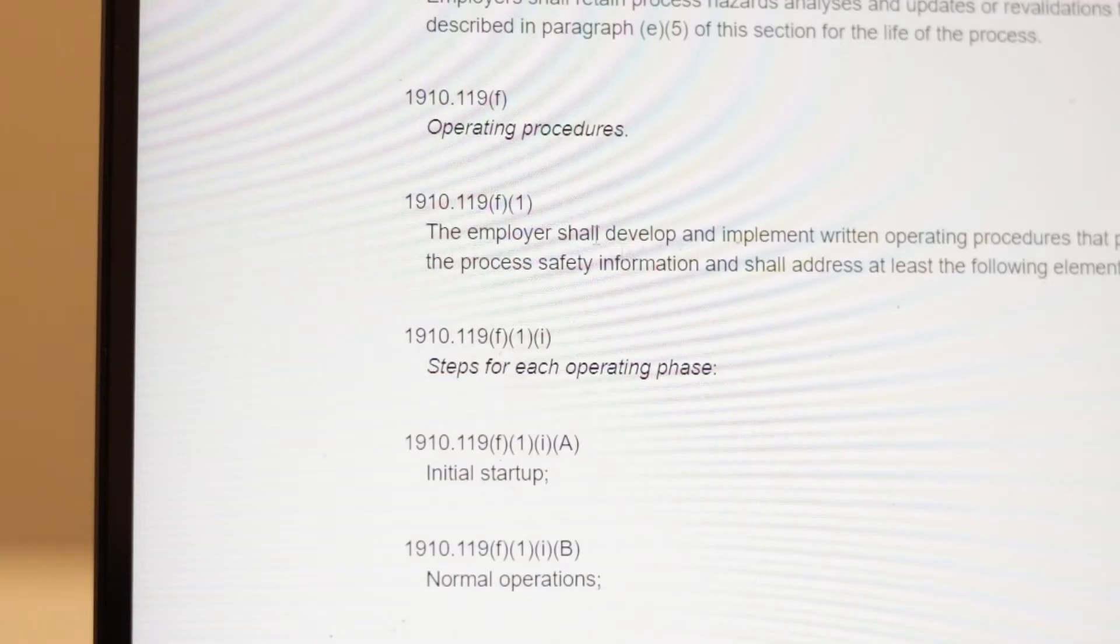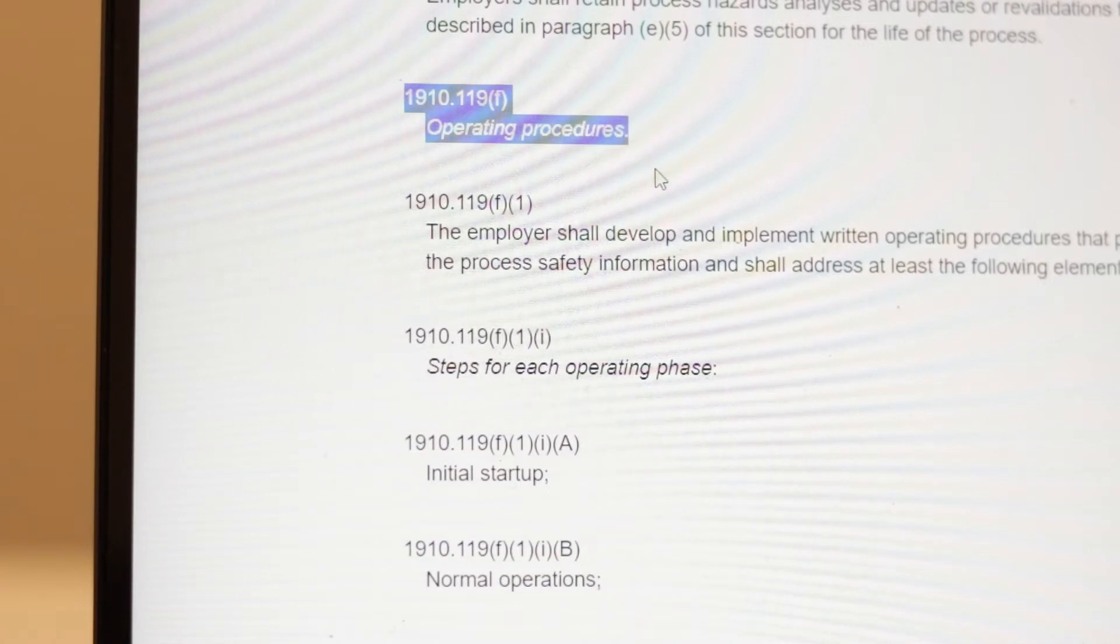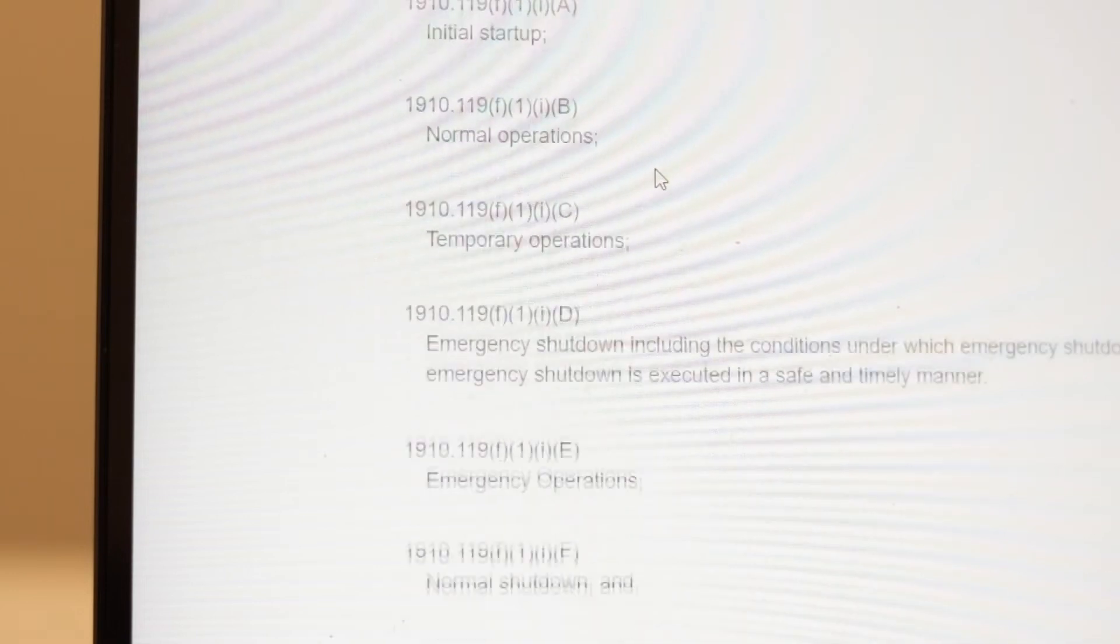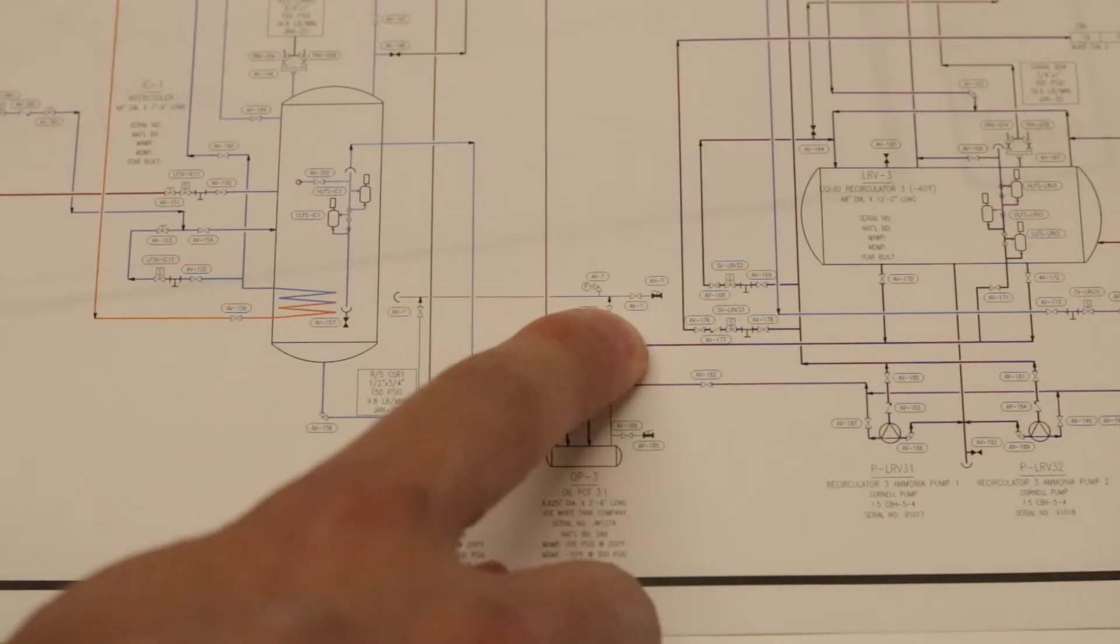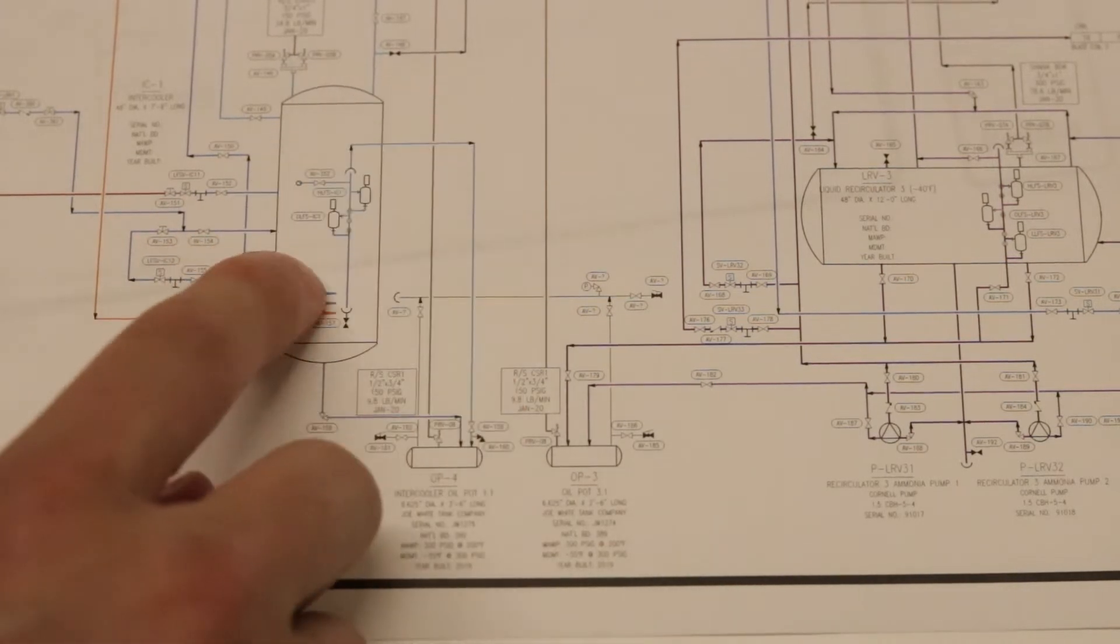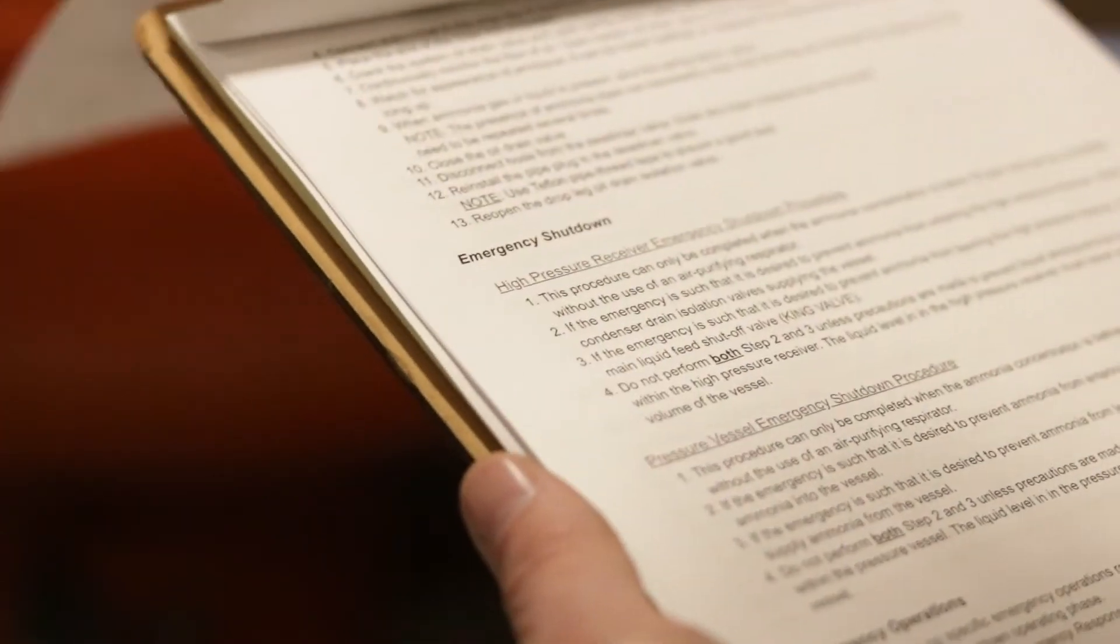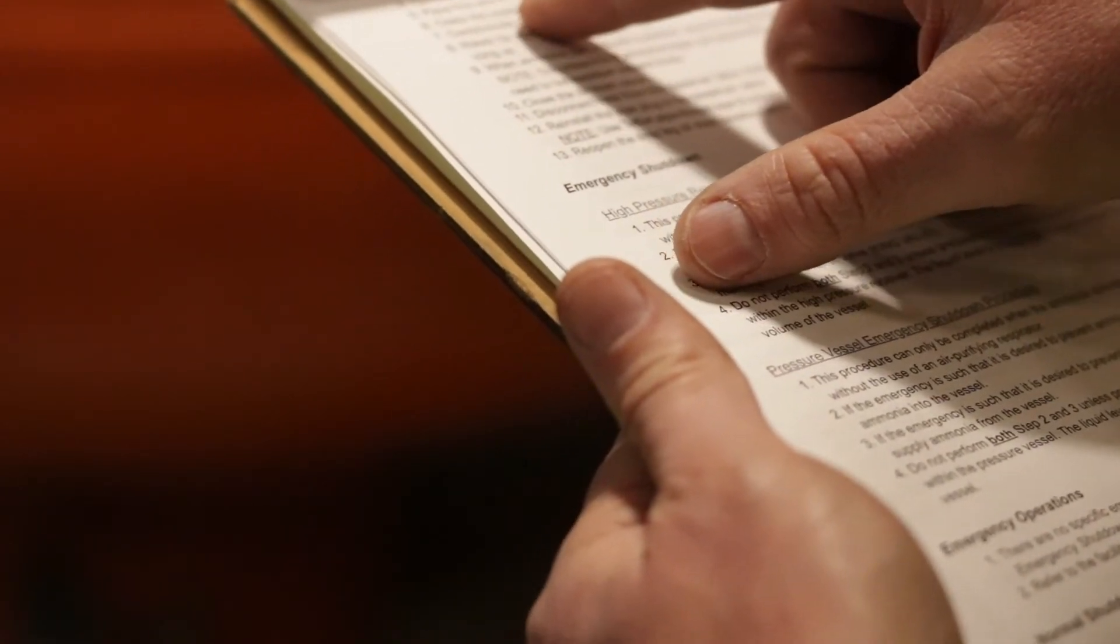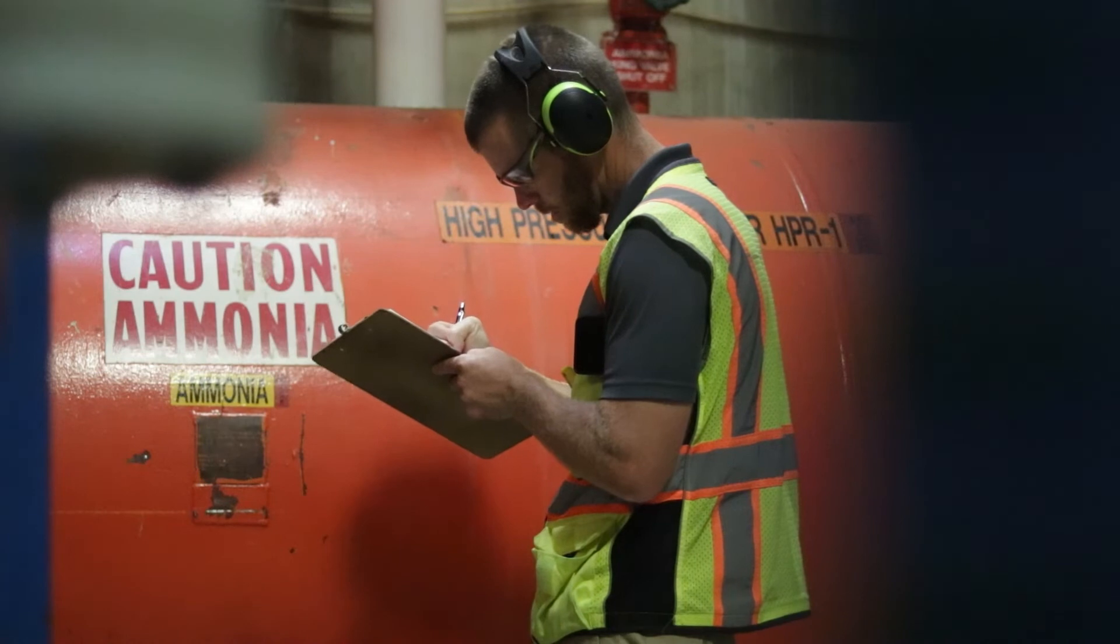Process safety regulations require that operating procedures be developed and implemented to provide clear instructions to safely conduct activities involved in a chemical process. The law requires that SOPs be consistent with the process safety information. If you accept the premise that P&IDs are the cornerstone of process safety information, then the requirements could be rephrased to say that SOPs must be consistent with P&IDs. Put another way, SOPs and P&IDs must not contradict each other.